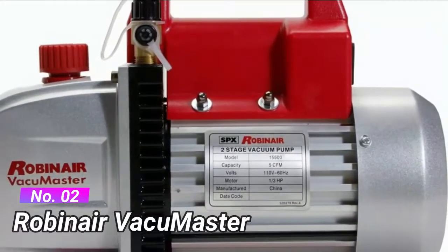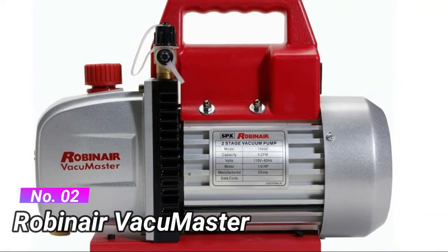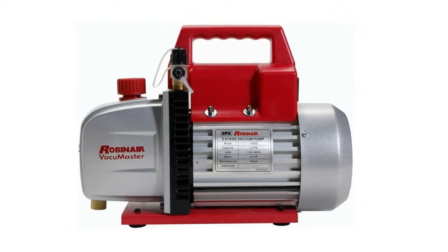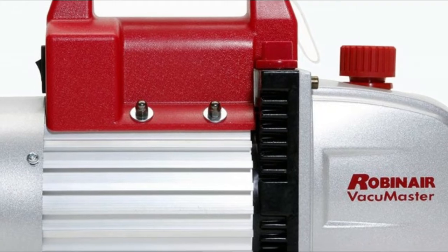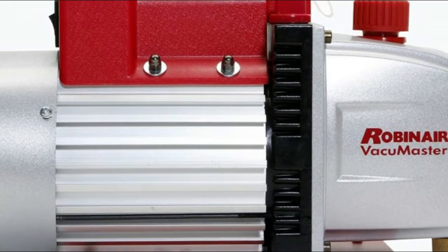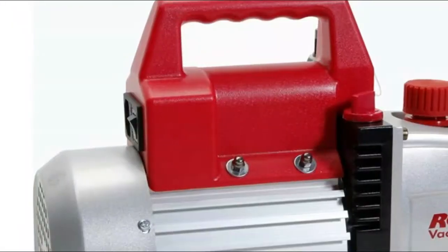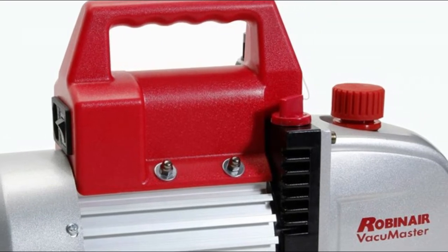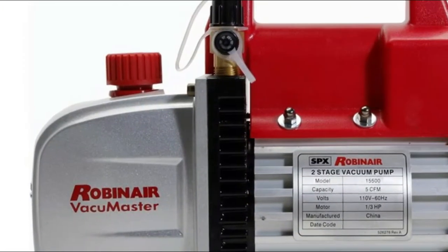Number 2. Robinair VacuMaster. Features an inlet fitting engineered for maximum airflow while preventing oil backflow, and finned aluminum surfaces that dissipate heat faster, keeping the pump cooler and extending life. Designed for air conditioning and refrigeration service, featuring a two-stage rotary vane design, 7.5-ounce oil capacity, and non-skid feet. 5 CFM free air displacement, factory rated to 35 microns. Easy-to-read sight glass, easy-access oil fill port, and angled oil drain valve for faster, more complete draining.